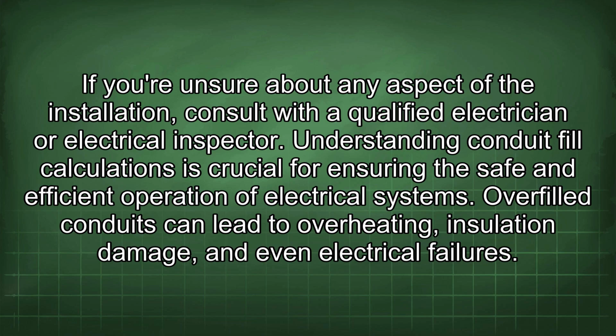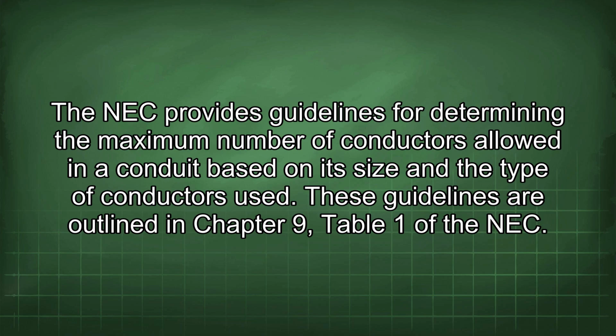Understanding conduit fill calculations is crucial for ensuring the safe and efficient operation of electrical systems. Overfilled conduits can lead to overheating, insulation damage, and even electrical failures. The NEC provides guidelines for determining the maximum number of conductors allowed in a conduit based on its size and the type of conductors used. These guidelines are outlined in Chapter 9, Table 1 of the NEC.